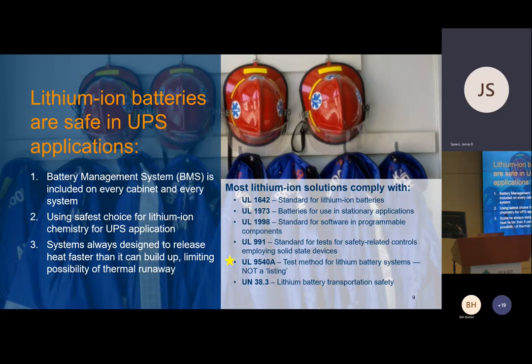On the left, the battery management system, which is required by fire code to be included on every lithium cabinet. It's the main reason we feel comfortable about the safety of these batteries. It monitors the battery and takes proactive action long before any temperature gets too high, or current gets too high, or voltage becomes too unbalanced.